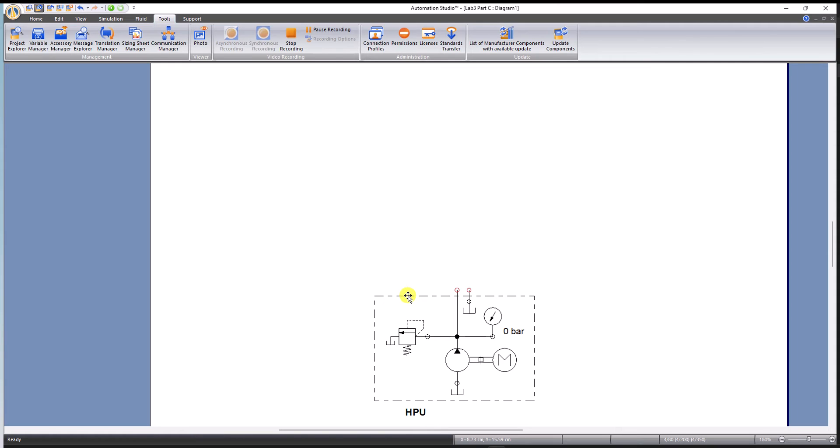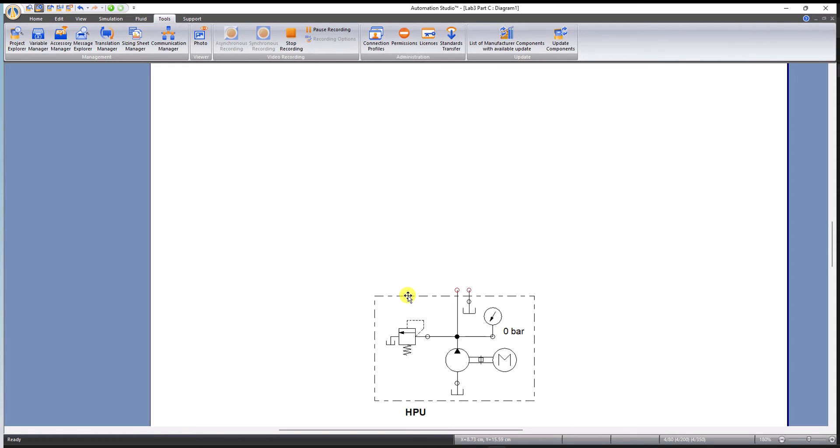We have some conditions: we have to use a 4 by 3 DCV which will allow the pump to keep running at low pressure while the hydraulic motor is stopped. So we're going to have to use a tandem center 4 by 3 DCV to fulfill this condition.